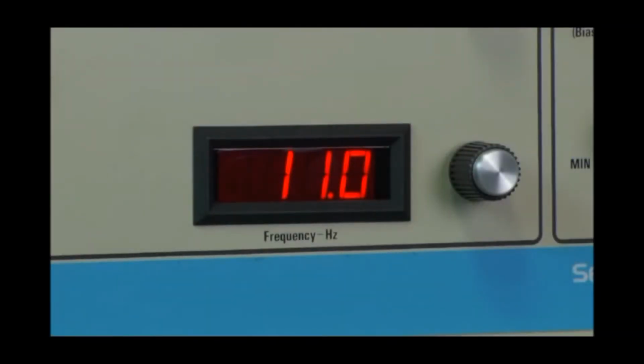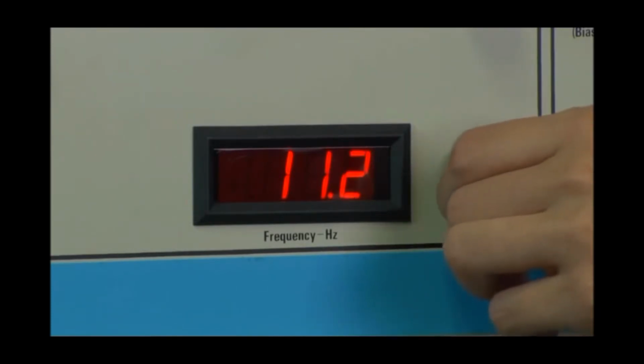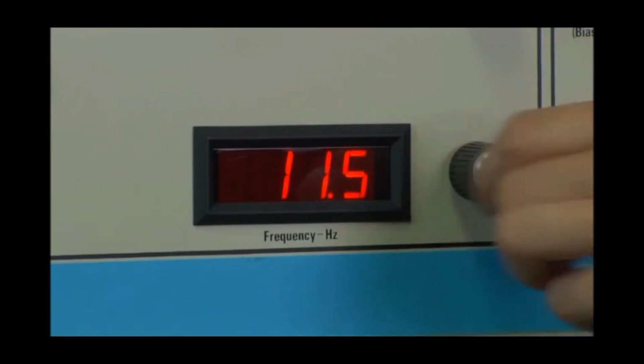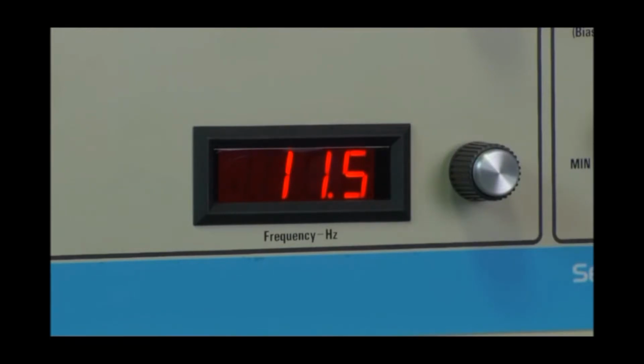Frequency. Typical neonatal applications utilize frequencies of 10 to 12 Hz, or 600 to 720 breaths per minute. Typically, larger patients require lower set frequencies.